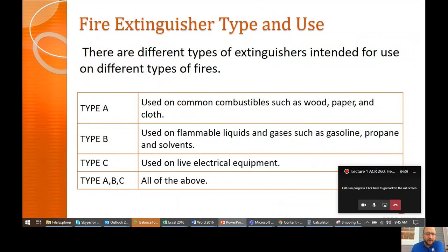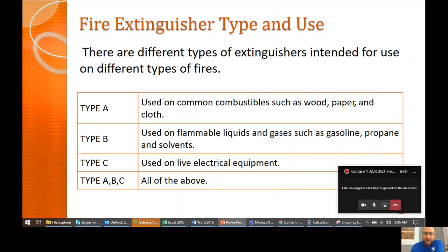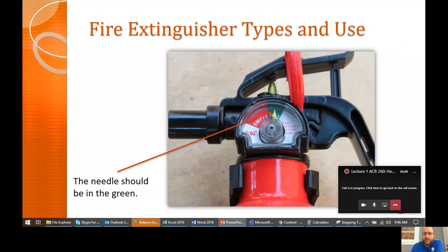Fire extinguisher types — they are rated for certain types of fires: Type A, Type B, Type C, and some have all types. You need to know what type to use on the right kind of fire. If you're working on electrical equipment, you wouldn't want to use a Type A because that uses basically water. For this class, Type B covers flammable liquids and gases such as propane, solvents, and natural gas. You probably keep one of these on your truck.